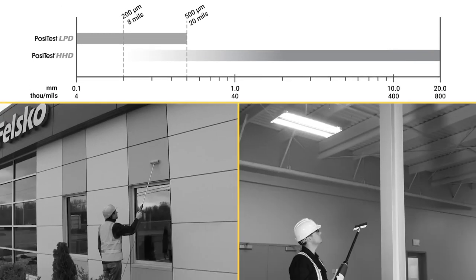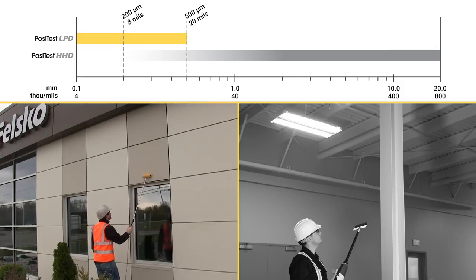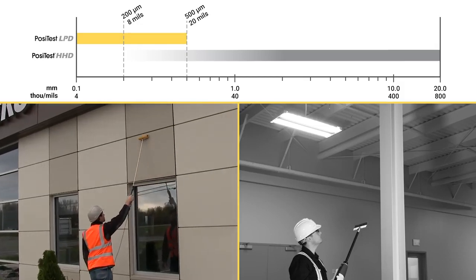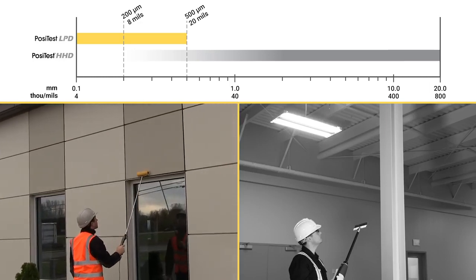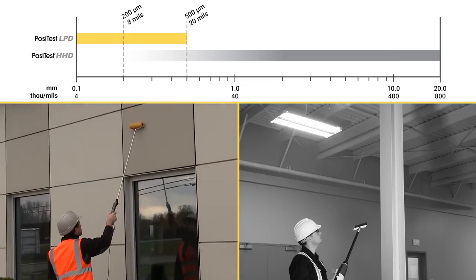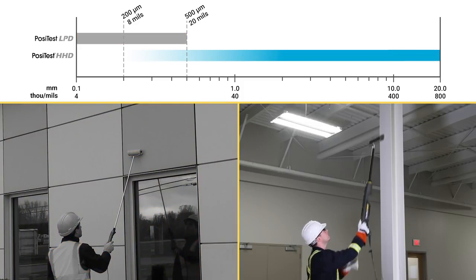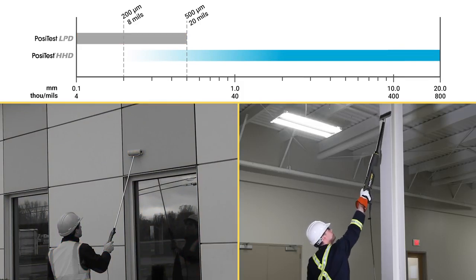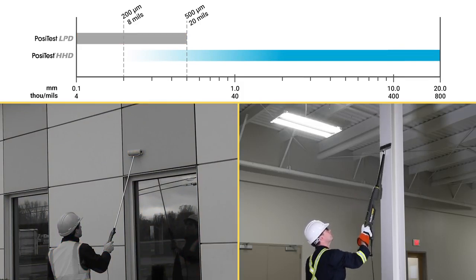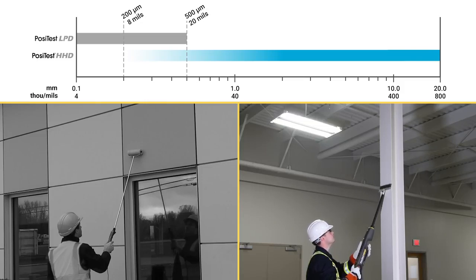The instrument used to detect these defects depends on the thickness of the applied coating. The Positest LPD low-voltage pinhole detector is ideal for finding defects in coatings less than 500 microns or 20 mils thick by emitting voltages below 100 volts through a moistened sponge. But for coatings in excess of 500 microns, a high-voltage detector is needed. Instead of a moistened sponge, a charged conductive brush or spring electrode is used.